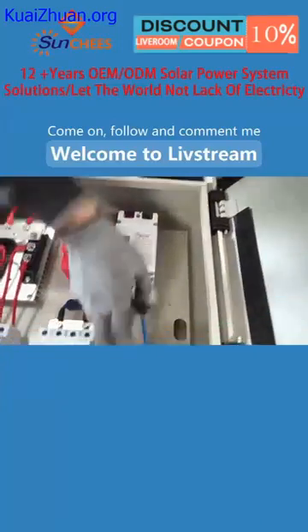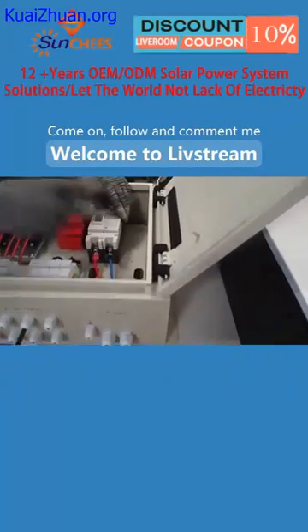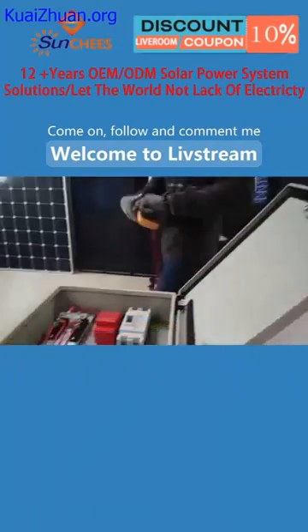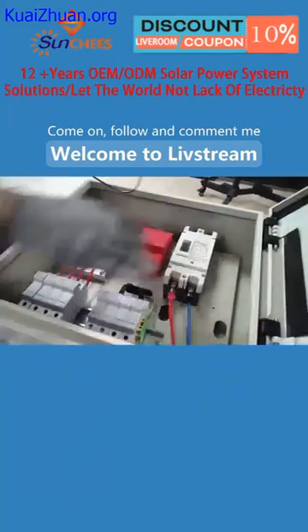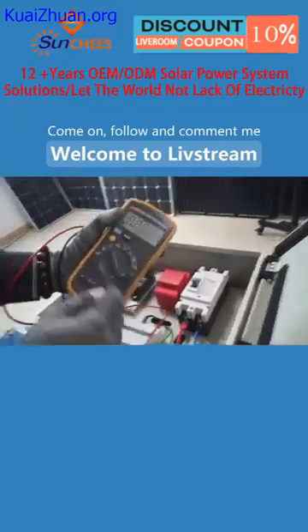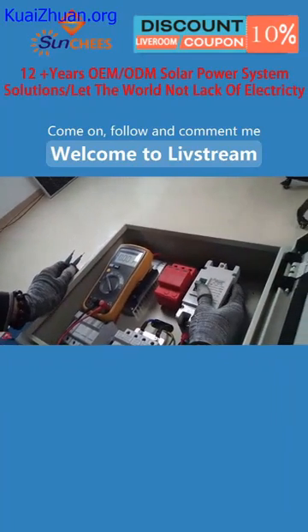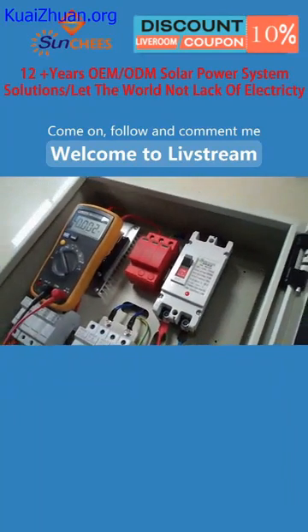Okay. After you finish the connection on the PV combiner side, remember to do one thing first. Use the multimeter to check the voltage. Use the multimeter to check the voltage of the PV combiner output port. Okay. Just turn the multimeter to the voltage icon. And then turn on the breaker, turn on the DC breaker. Okay, and you check the voltage.